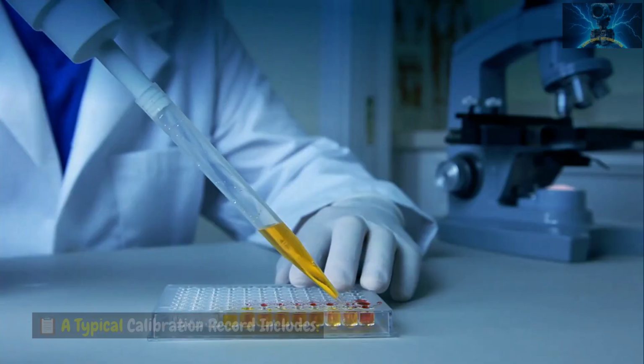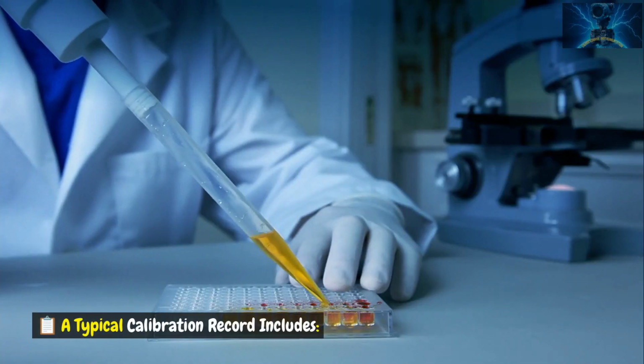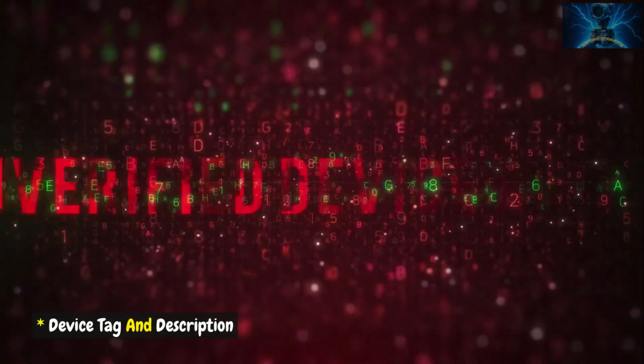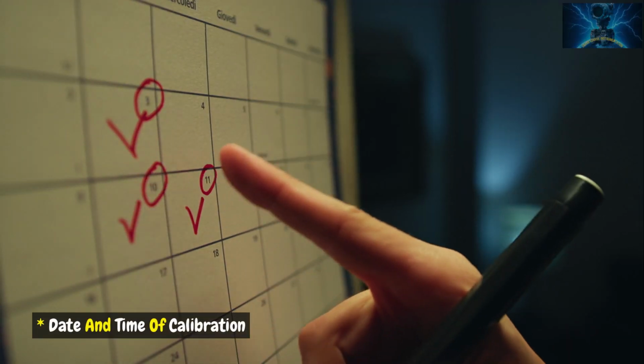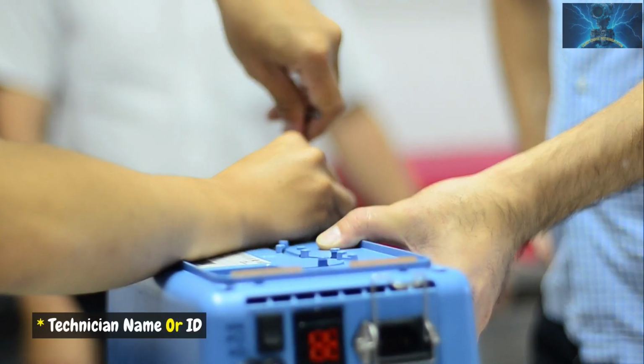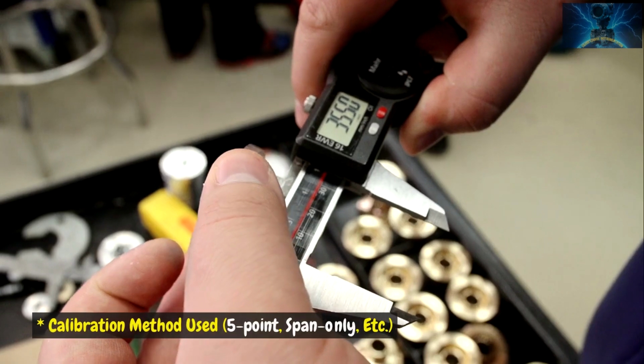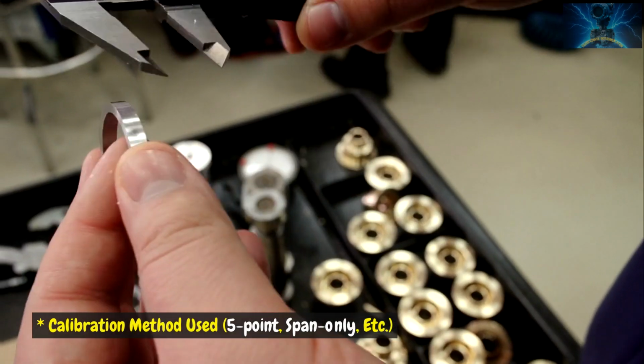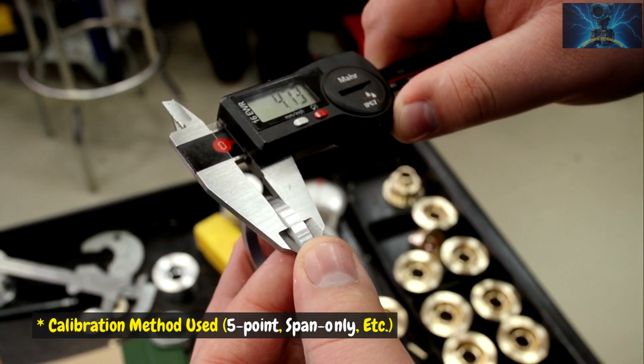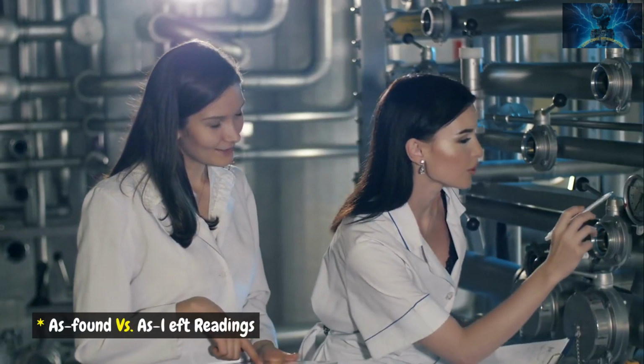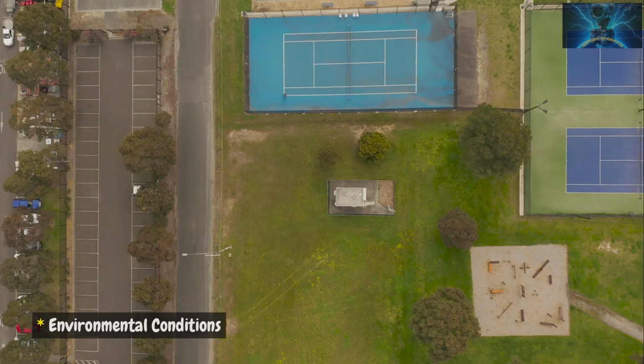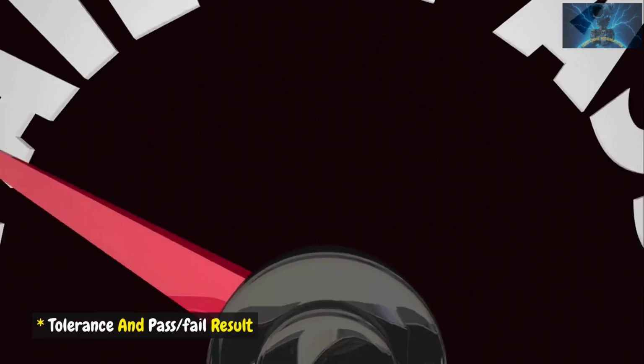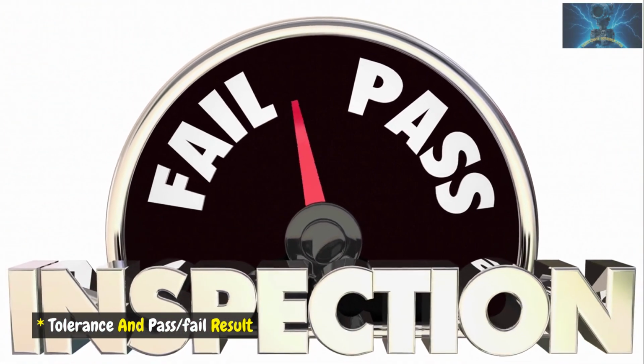and legal traceability. A typical calibration record includes device tag and description, date and time of calibration, technician name or ID, calibration method used, 5-point, span only, etc., as found versus as left readings, environmental conditions, tolerance and pass-fail result.